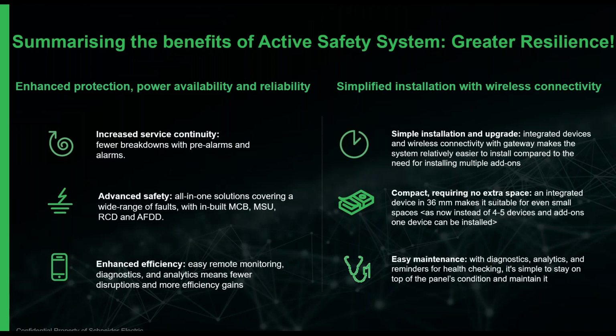To summarize the benefits of the active safety system, we're really getting greater resilience. We're getting enhanced protection, power availability is improved, and reliability is improved. So what we can say is we're getting increased service continuity because there's fewer breakdowns, because the pre-alarms and alarms help you stay on top of it before the problems occurred. It's got advanced safety because it's got all-in-one solutions covering a wide range of faults, whether it's short circuit, overload, over voltage, residual current issues, arc fault issues. It's all in that one device.